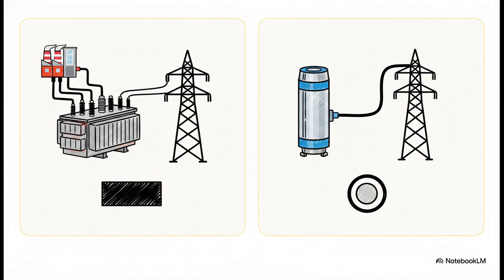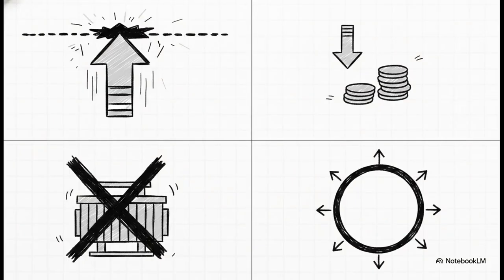But then, in 1998, the Swiss company ABB invented something called the Powerformer. A Powerformer can actually generate high voltages directly. We're talking up to 400 kilovolts right out of the machine. This means it connects directly to the high-voltage grid, completely eliminating the need for a step-up transformer altogether. To pull this off, they replaced the old rectangular conductors with high-voltage XLPE circular cables right inside the stator. And guys, this isn't just a neat parlor trick. It is an absolute game changer, giving us 4 massive benefits.